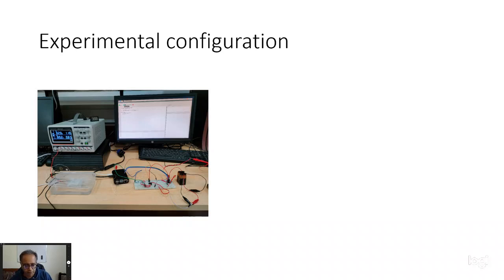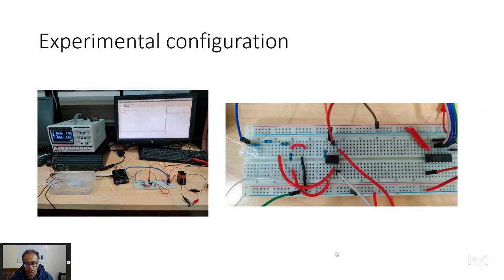parameters fixed, right? So what that means is, in this experimental configuration, if we just focus on our circuit configuration, on the first end we have the Wheatstone bridge. So here you can see the current limiting resistor, and this is the Wheatstone bridge configuration. This is the PT100 resistor which is coming in and attaching to the Wheatstone bridge, and now you have the outputs, the VB and the VD outputs, which are connected to the instrumentation amplifier.